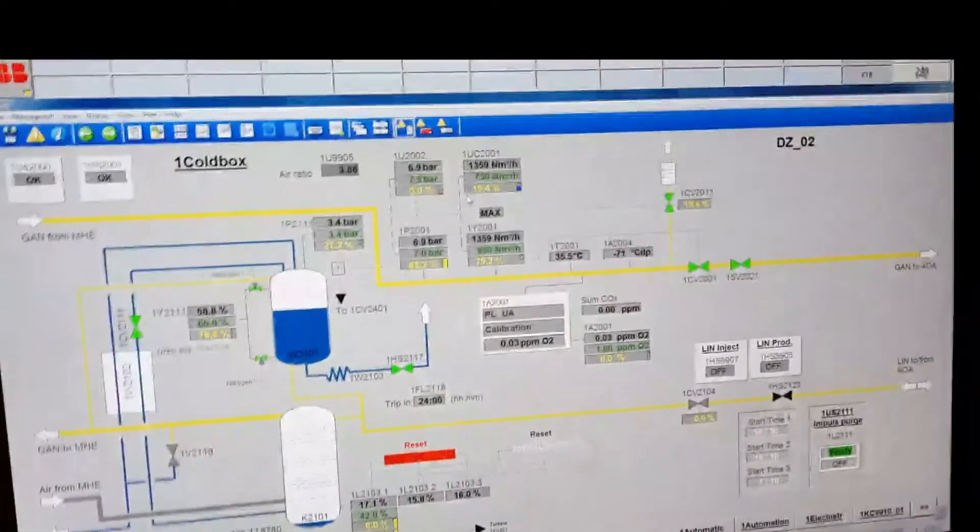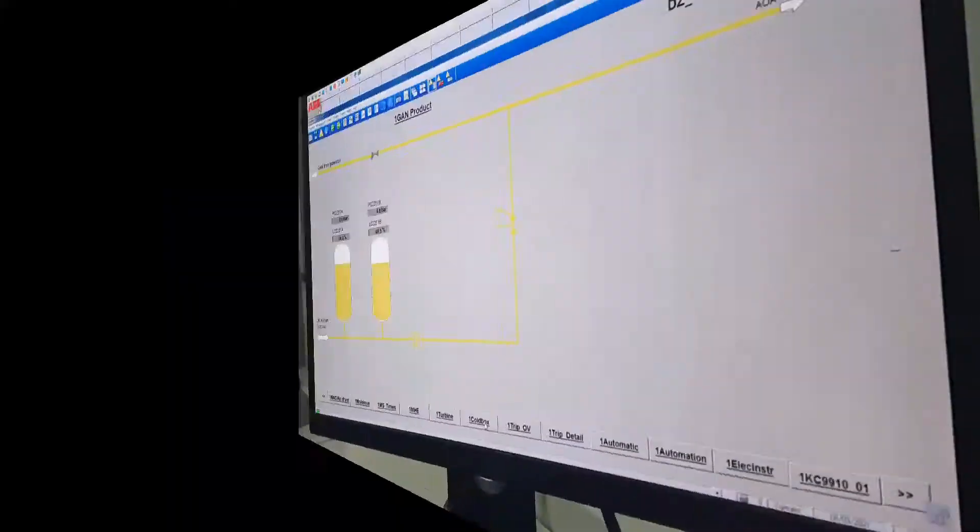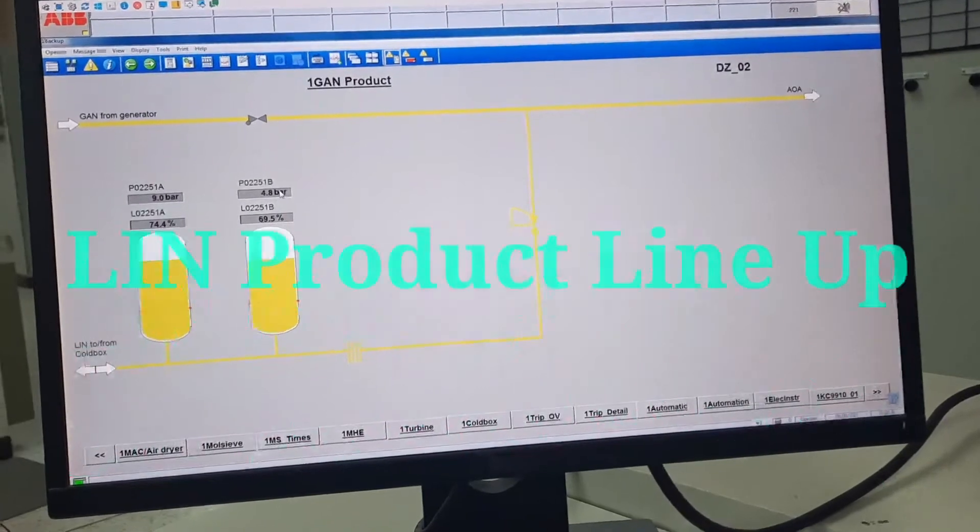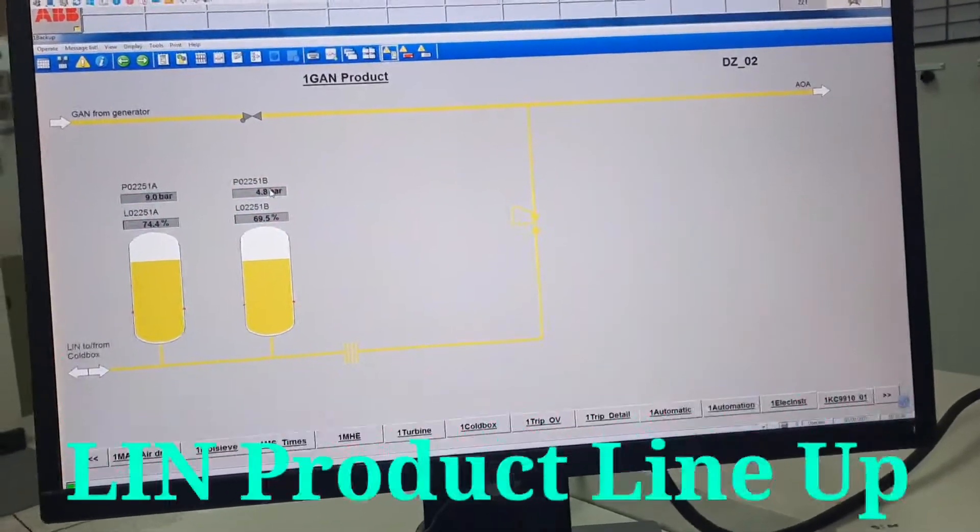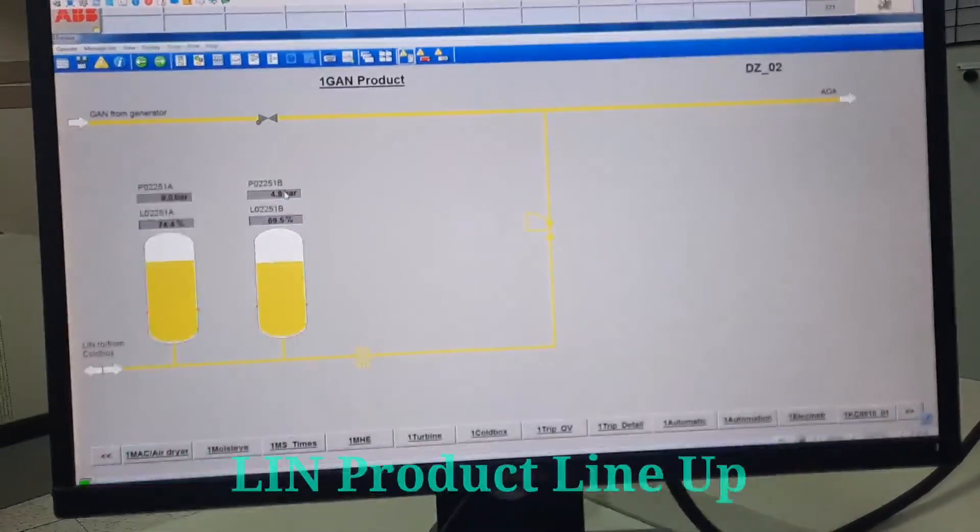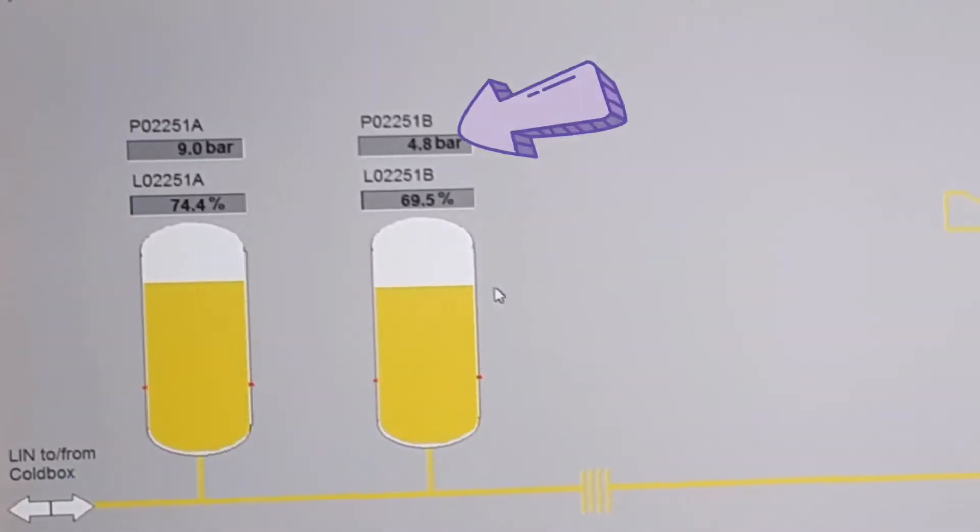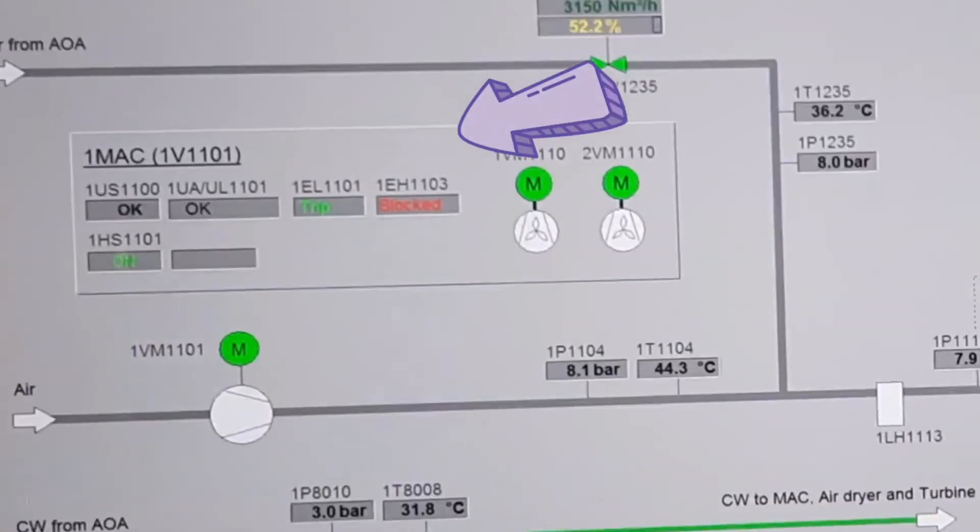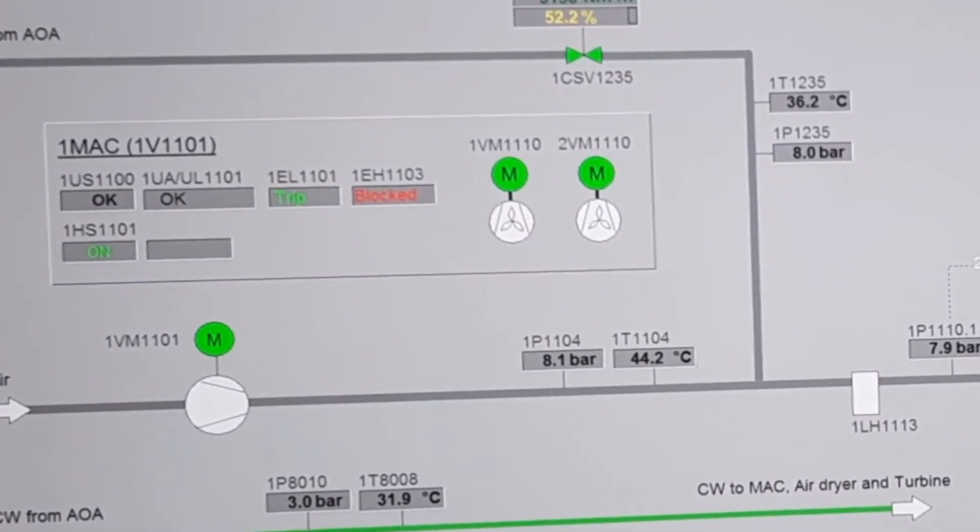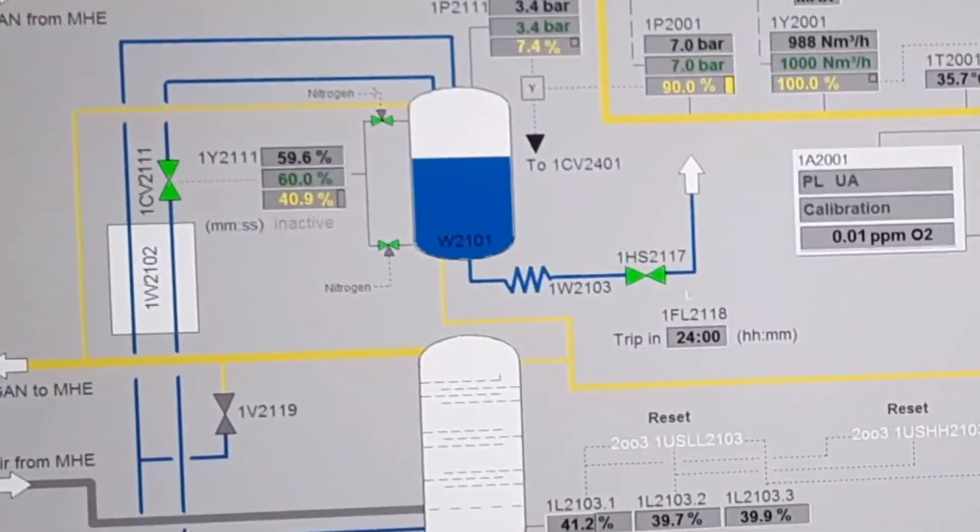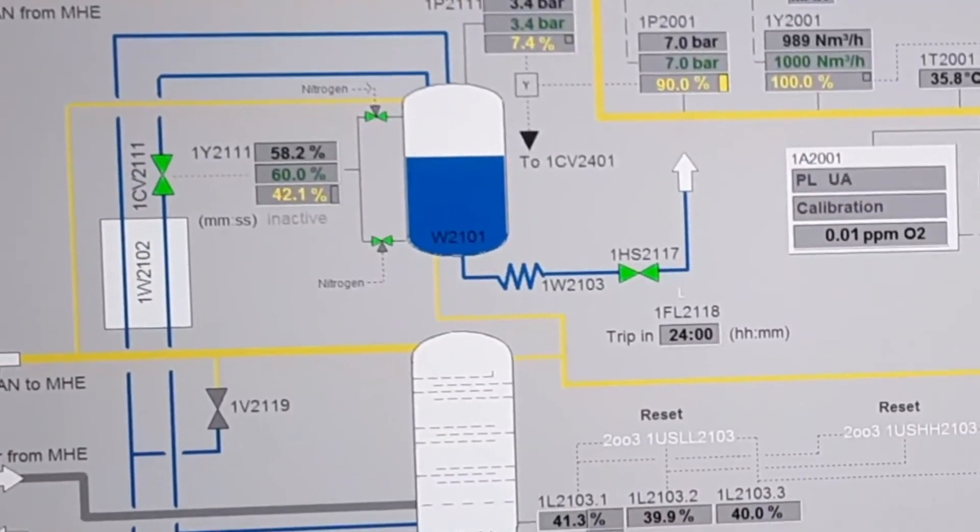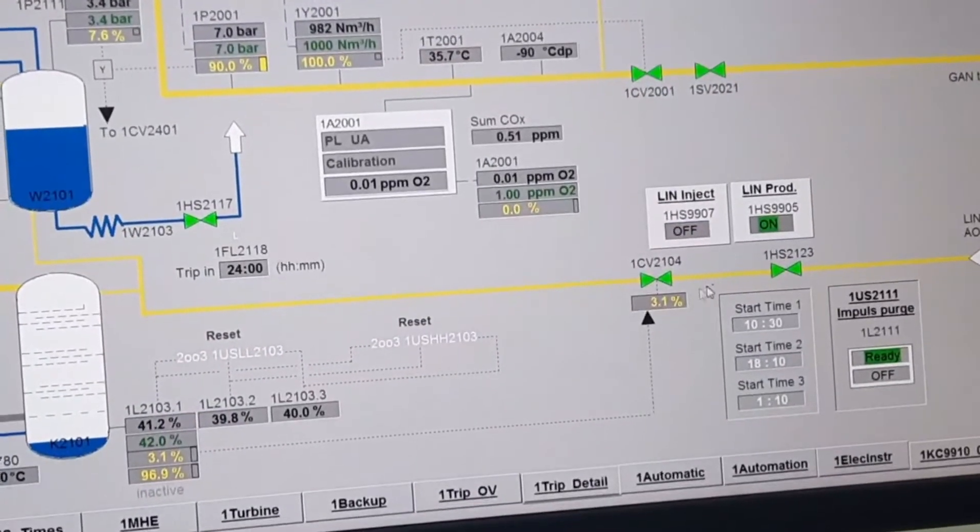Before lining up the liquid line, we need to check that the receiving tank pressure is less than 7 kg. This shows 4.8 kg, so it's acceptable. Now I will go to the cold box unit and line up the liquid line.